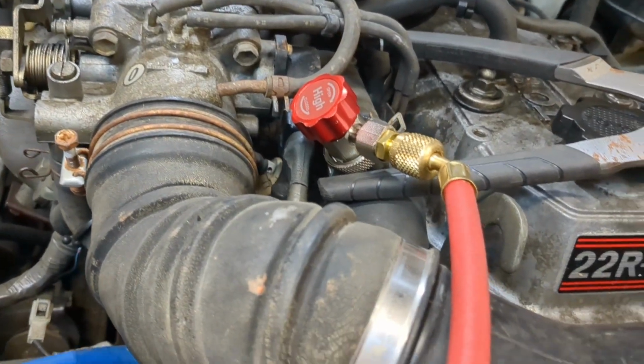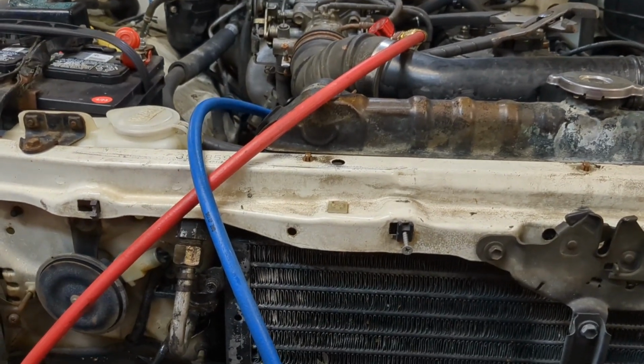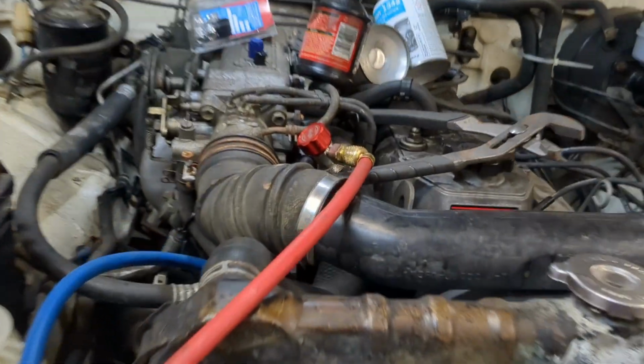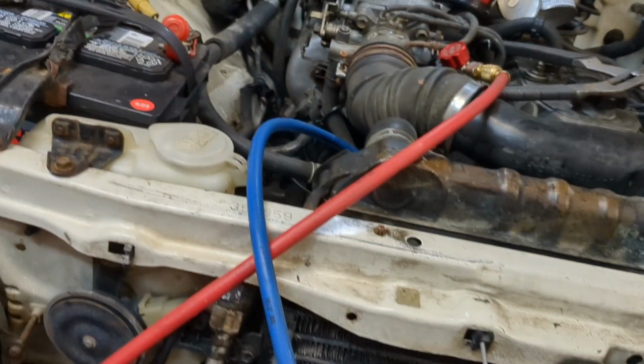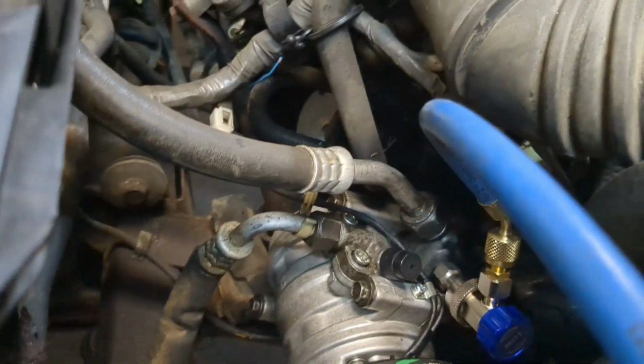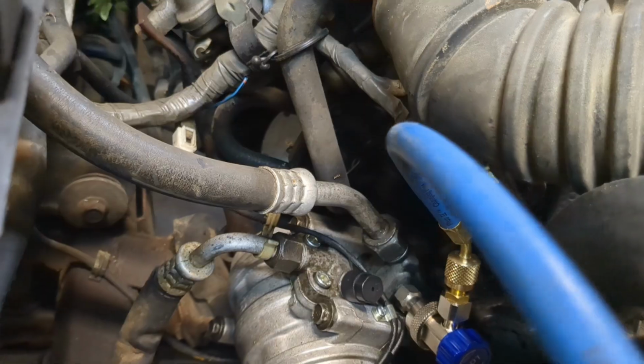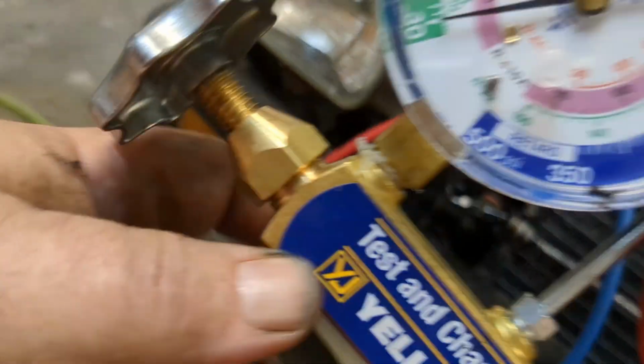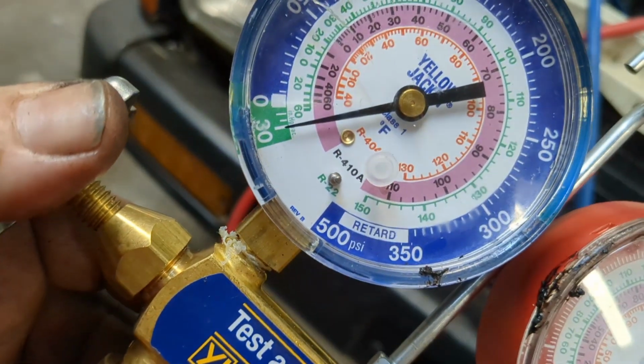Sometimes these crank-down 134 fittings do not seal off correctly at the fitting, so you can actually be pulling a vacuum and just pulling air right through the high side. So what I did is I took the high side off and left it off, put a service cap on the new port I installed, tightened that down, and I'm just pulling the vacuum through the low side, making sure it's tight.